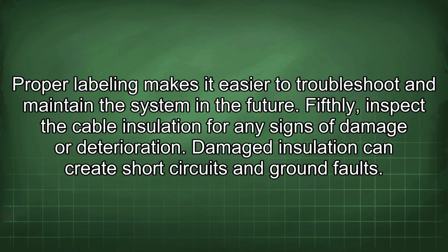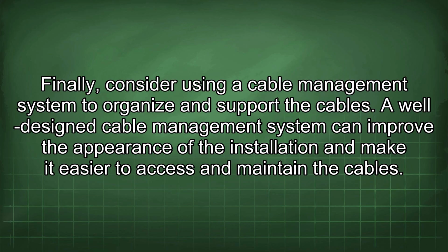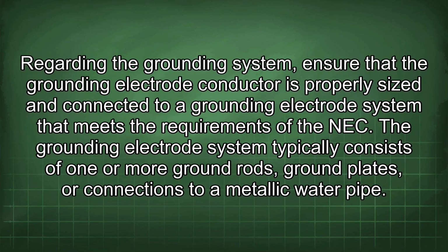Fifthly, inspect the cable insulation for any signs of damage or deterioration. Damaged insulation can create short circuits and ground faults. Finally, consider using a cable management system to organize and support the cables. A well-designed cable management system can improve the appearance of the installation and make it easier to access and maintain the cables. Regarding the grounding system, ensure that the grounding electrode conductor is properly sized and connected to a grounding electrode system that meets the requirements of the NEC.